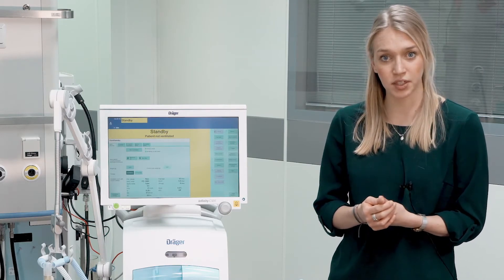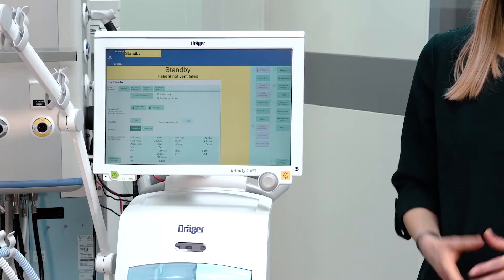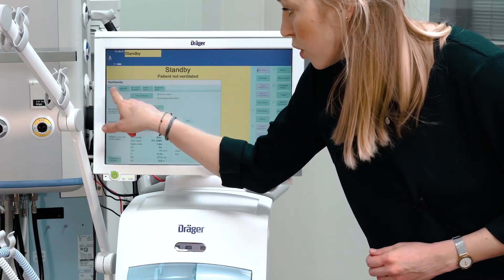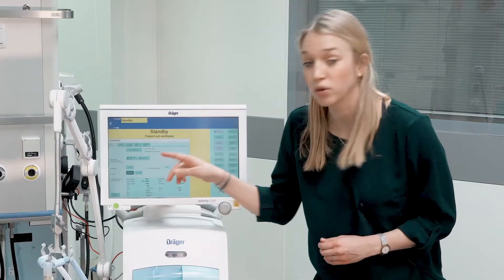Tube for invasive ventilated patients, non-invasive ventilation, and O2 therapy. You can initially set the therapy type via the menu Tube NIV or on the main page via O2 therapy.